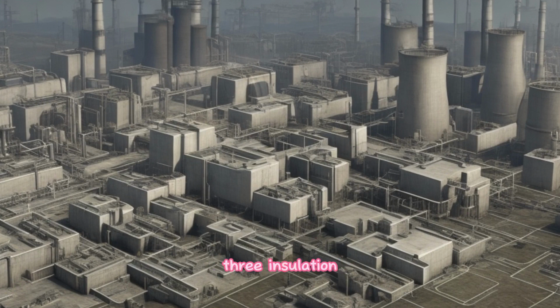3. Insulation degradation. Insulation resistance testing and high-potential (hipot) testing are effective in detecting insulation degradation in cables. Over time, cables can experience insulation breakdown due to factors like aging, environmental conditions, or chemical exposure. Cable testing techniques can identify weakened insulation, which can lead to electrical leakage, reduced insulation resistance, and potential short circuits or malfunctions.